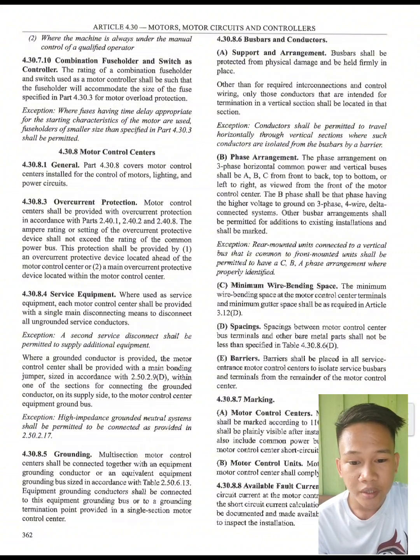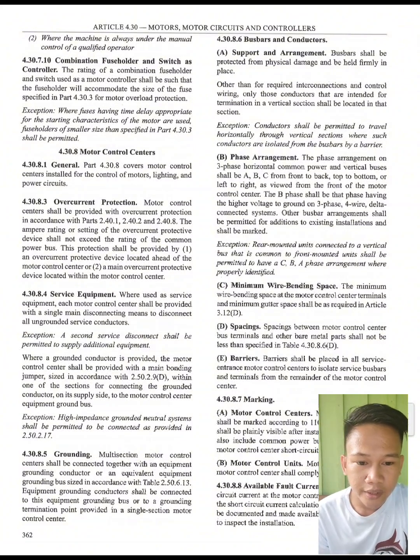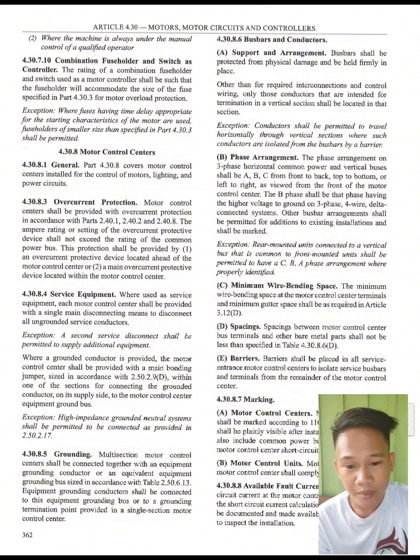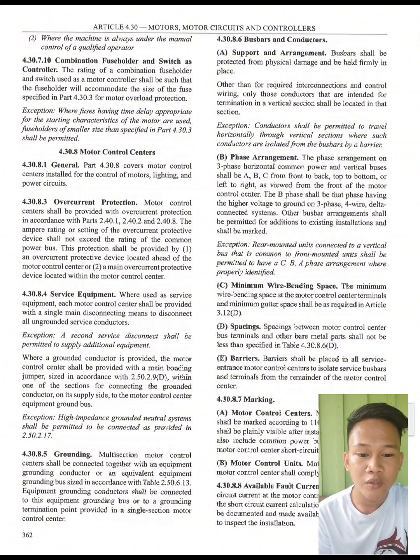Next, we have 4.30.7.10 Combinations of fuse holder and switch as controller. The rating of a combination fuse holder and switch used as a motor controller shall be such that the fuse holder will accommodate the size of the fuse specified in Part 4.30.3 for motor overload protection. Exemption: where fuses having time delay appropriate for the starting characteristics of the motor are used, fuse holders of smaller size than specified in Part 4.30.3 shall be permitted.